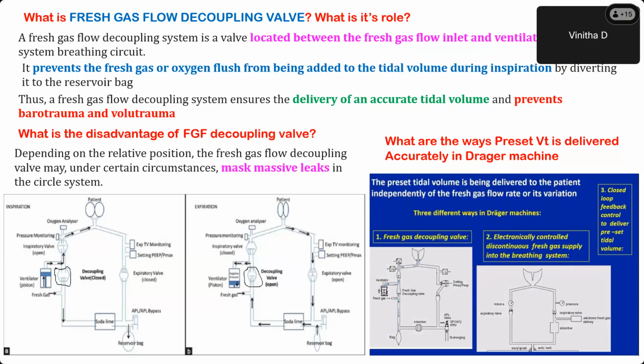So there are three methods by which a Draeger machine can deliver. One is by fresh gas decoupling. I told you, it is present in Draeger. So that is the valve that is currently there. In other machines, there is electronically controlled discontinuous fresh gas supply into the breathing system, and there is a closed loop feedback control to deliver the preset tidal volume. So these are the three methods, not in the same machine, but different manufacturers use different technologies.